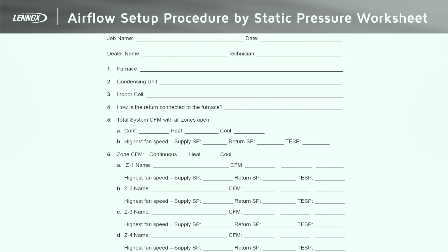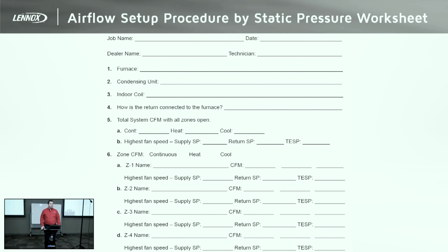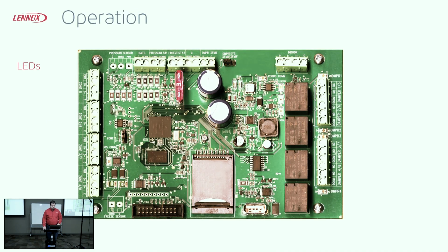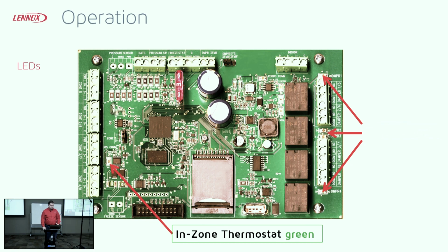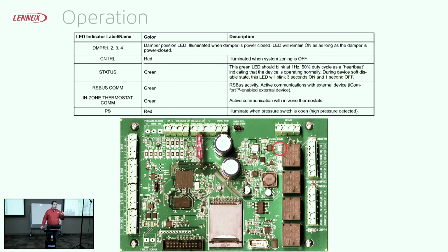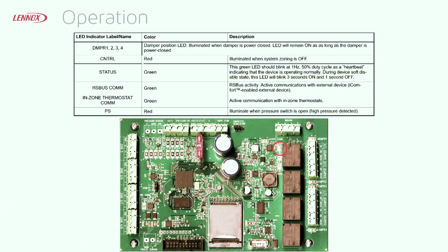There's a static pressure worksheet that can be a good thing to fill out. It shows your static pressure for each one of those zones, which can save your bacon in the future. If there are problems down the road or somebody changes something, it shows that everything was working at startup and within tolerance. So we talked a little bit about the LEDs. I'm not going to go over that too much again; that's clear in the installation instructions. But usually if everything's working, the green light is going to be on, indicating that everything's functional.